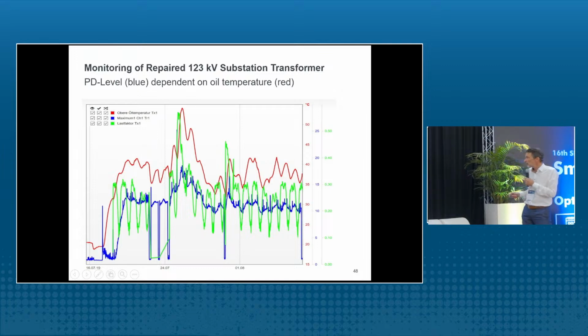You can see here some results. In red, you can see the oil temperature of the transformer. In green, you can see the loading of the transformer. So this is one day. You have a high load during daytime, low load in the early morning. And the blue curve is the PD level. Here in this case, the transformer was switched off, then you have, of course, a low PD level. But here you can see very nicely that the blue curve and the red curve are more or less in parallel. So PD behavior is dependent on temperature.